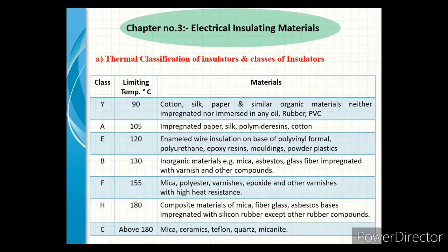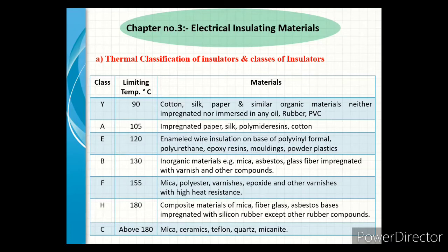The first class is thermal withstand ability. In this class, insulating materials are classified into seven categories: Y class, A class, E class, B class, F class, H class, and C class — each depending on limiting temperature range. The first class, Y class, has a limiting temperature of 90°C. Materials included are cotton, silk, paper, and similar organic materials neither impregnated nor immersed in any oil, rubber, and similar things.